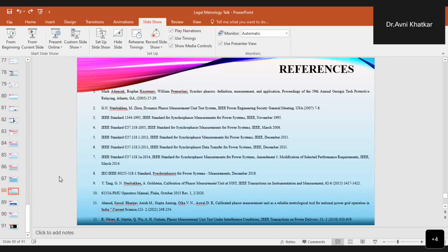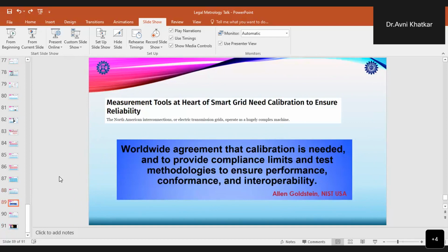These are various references which are being used. So also the North American interconnections, or the electrical transmission grid, which operates as a hugely complex machine, also say that measurement tools at the heart of the smart grid need calibration in order to ensure reliability. And Alan Goldstein, who is working on PMUs at NIST USA, stated that there is worldwide agreement that calibration is needed, and that compliance limits and test methodologies are required to ensure performance, conformance, and interoperability.